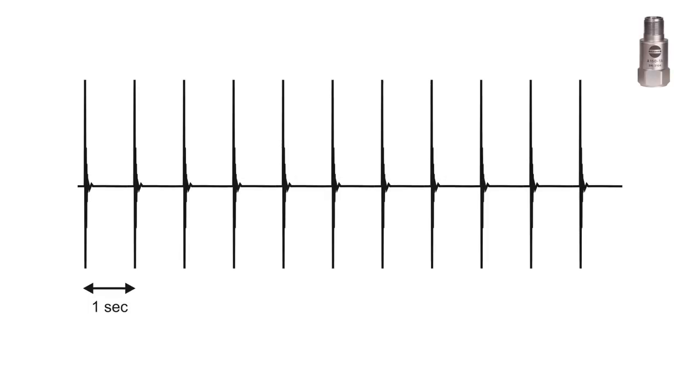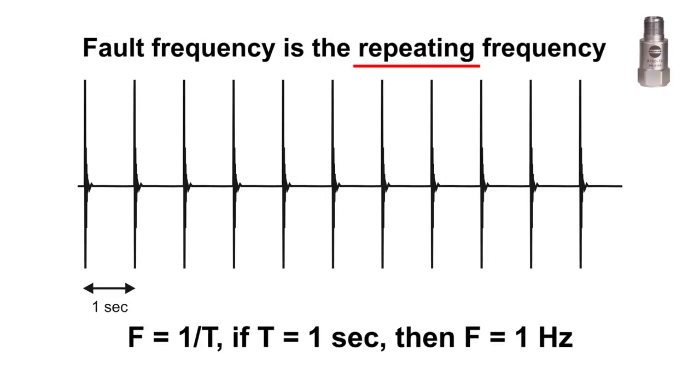The fault frequency is the repeating frequency of shocks. It is not pure sine frequency which should be captured by sensor. We need to measure the natural frequencies of shocks. As I told you, they are higher than 500 Hz.